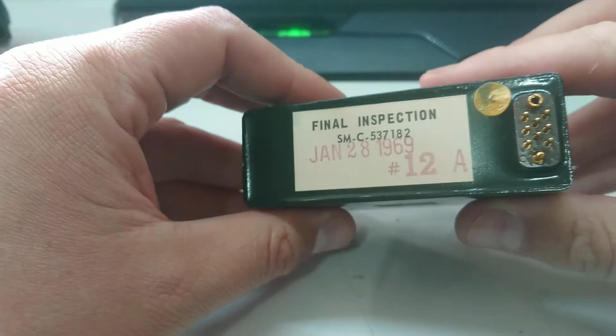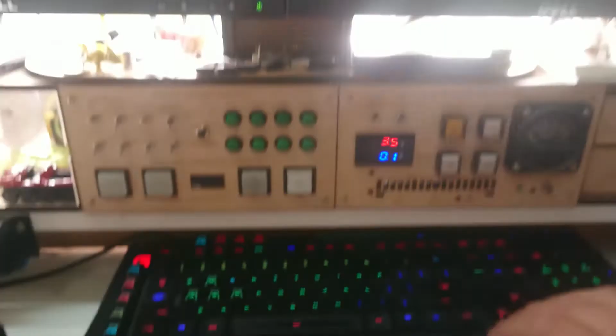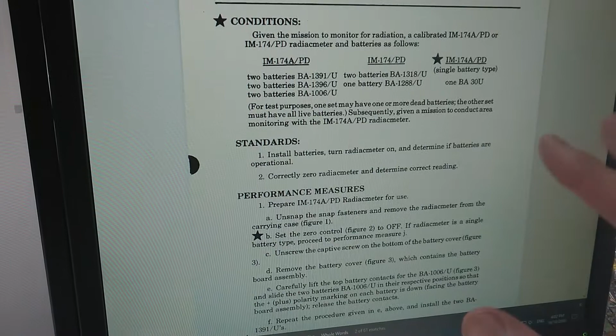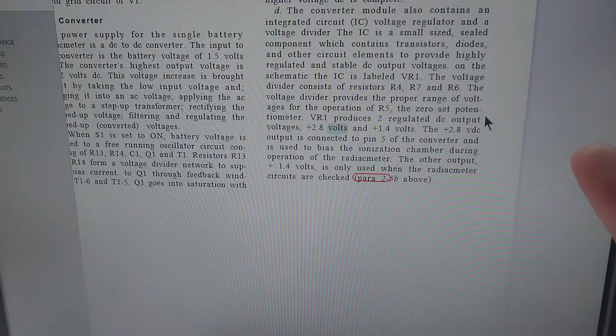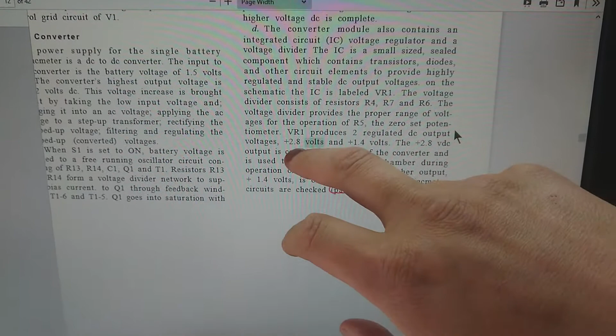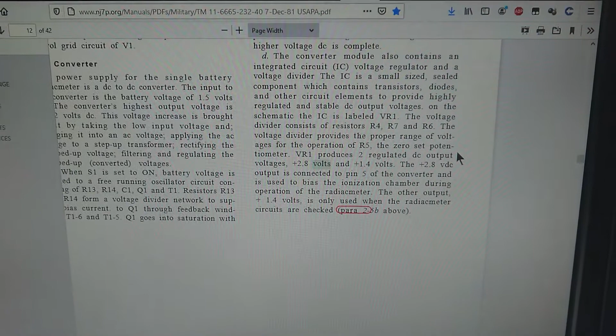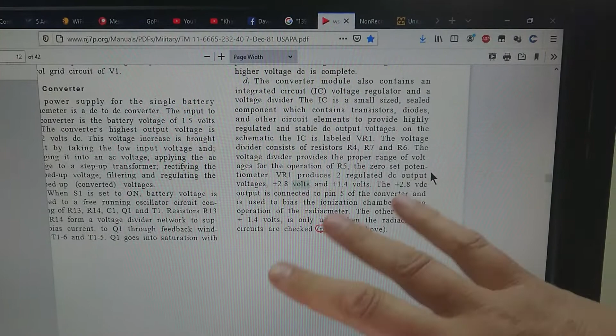So ionization chamber and all, which is kind of handy if you are fixing these things in the field. You can rip the chamber out and plug a new one in very quickly. Now, the other thing that happened, I did a little bit of research and I found one of the original training manuals for field use for this unit, and I also over here found the original service manual for it, and it also tells me what the voltages are. So we have 2.8 volts, 1.4 and 2.8. So that was a push and a pull circuit. It also tells me where everything connects and what it should be.